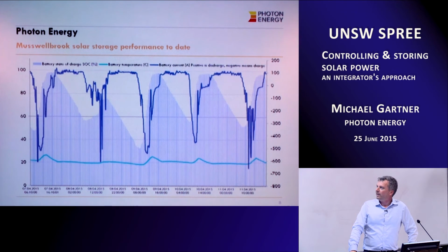So what happens is we charge the batteries very fast, and we get to a point at about 2 p.m. in the afternoon, I think in summer, where the batteries are fully charged. They go into float cycle, and the excess power from the solar system is no longer used, or it just passes through the whole circuit. It's a DC coupled circuit, so it basically passes through the inverters straight into the power consumption. Then as we go throughout the day, we get to a point where the batteries start to discharge, and you can see the state of charge there.